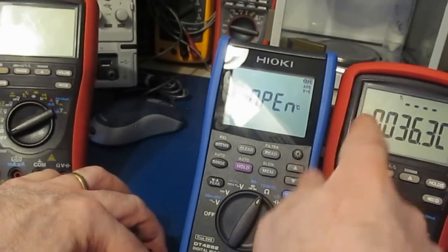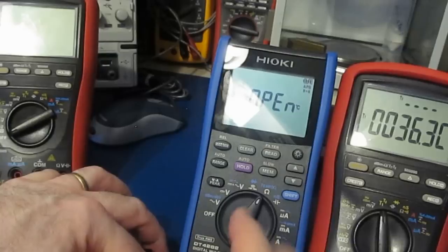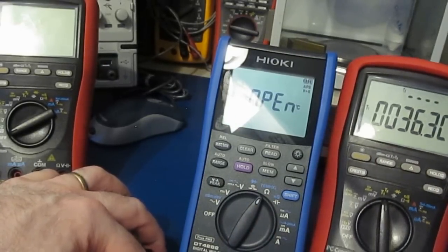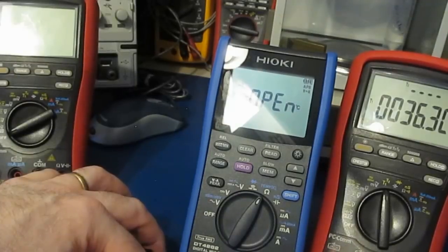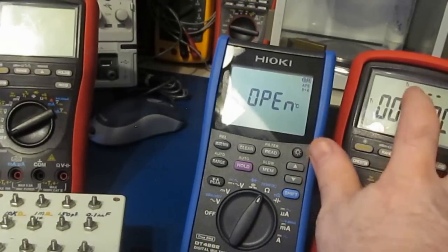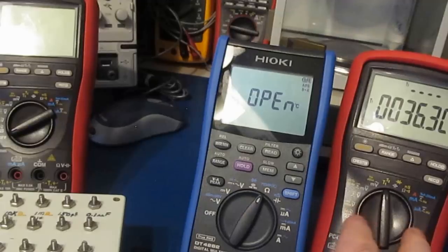Now, one of the key reasons that I bought this meter—you'll notice it has T1 and T2, so this meter actually has 2 thermocouple inputs. The second channel is on the 2 current jack, so you put a K-type thermocouple across the 2 current inputs, and that gets us T2. The other thing with this meter is it can look at the difference between these 2 probes.